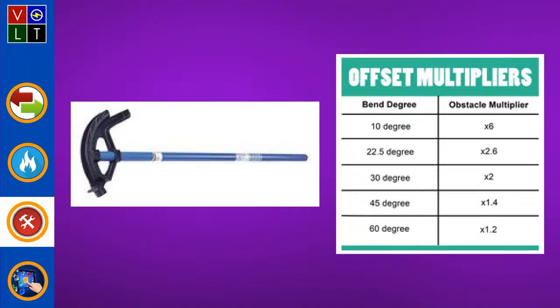If you want to do a 30-degree offset with a 10-inch rise, then you're going to do 20 inches between your marks. Typically, if you want to do a 10-inch rise, you want a more extreme angle, more like a 45-degree, because if you do a 10-inch offset in 20 inches, it's going to take way too long for that offset to happen. A lot of times when we do these offsets, we want them to happen fast. I typically use 45s, but you have to keep in mind, you have a 45, another 45, another 45, and another 45. You have 180 degrees in a 4-point saddle.